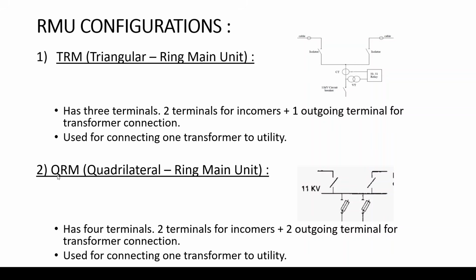Then the quadrilateral ring main unit is basically an RMU with 2 outgoings, therefore enabling to connect 2 distribution transformers to the ring network. So it has 4 terminals, 2 terminals for incomer. As you can see, my cable is coming from here usually, then it will continue. So 2 terminals for incomer and 2 outgoing terminals for transformer connection. This is a mistake here actually. It's used for connecting 2 transformers to utility.